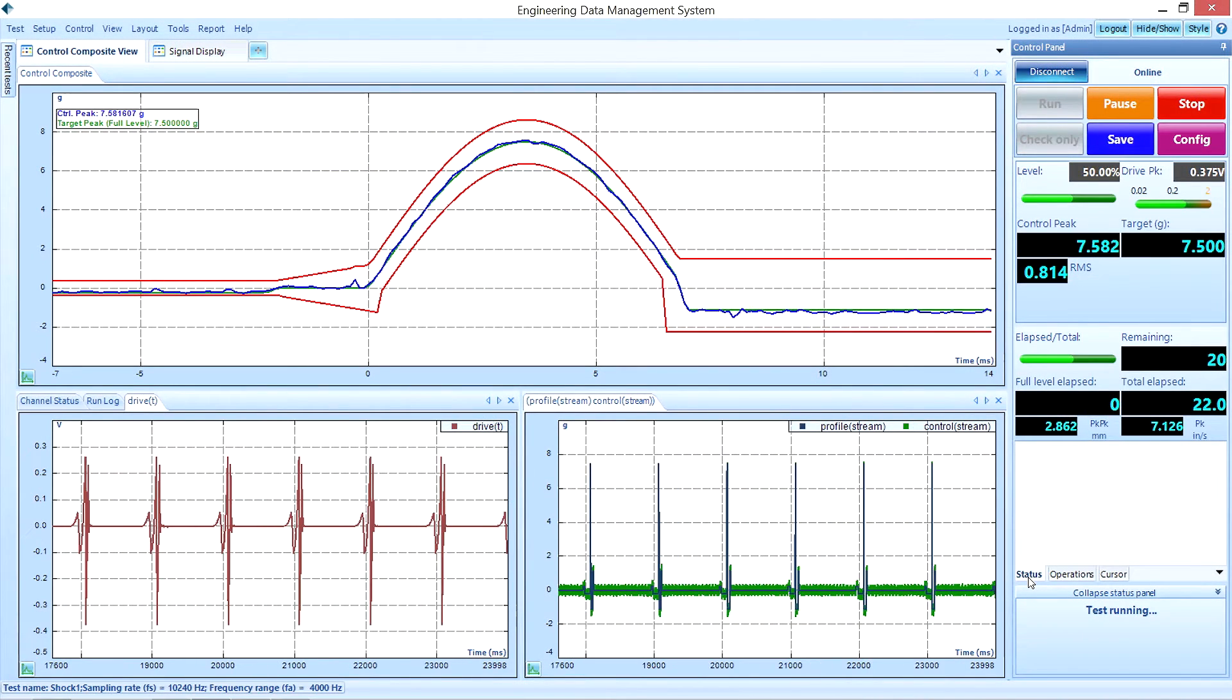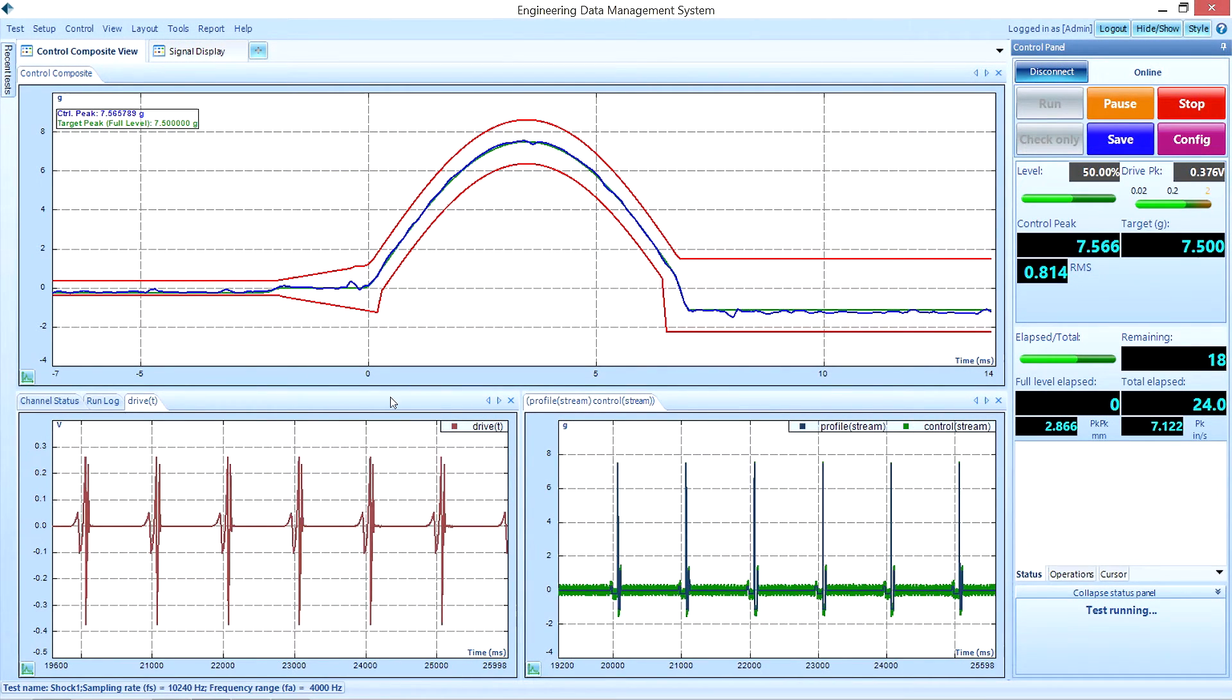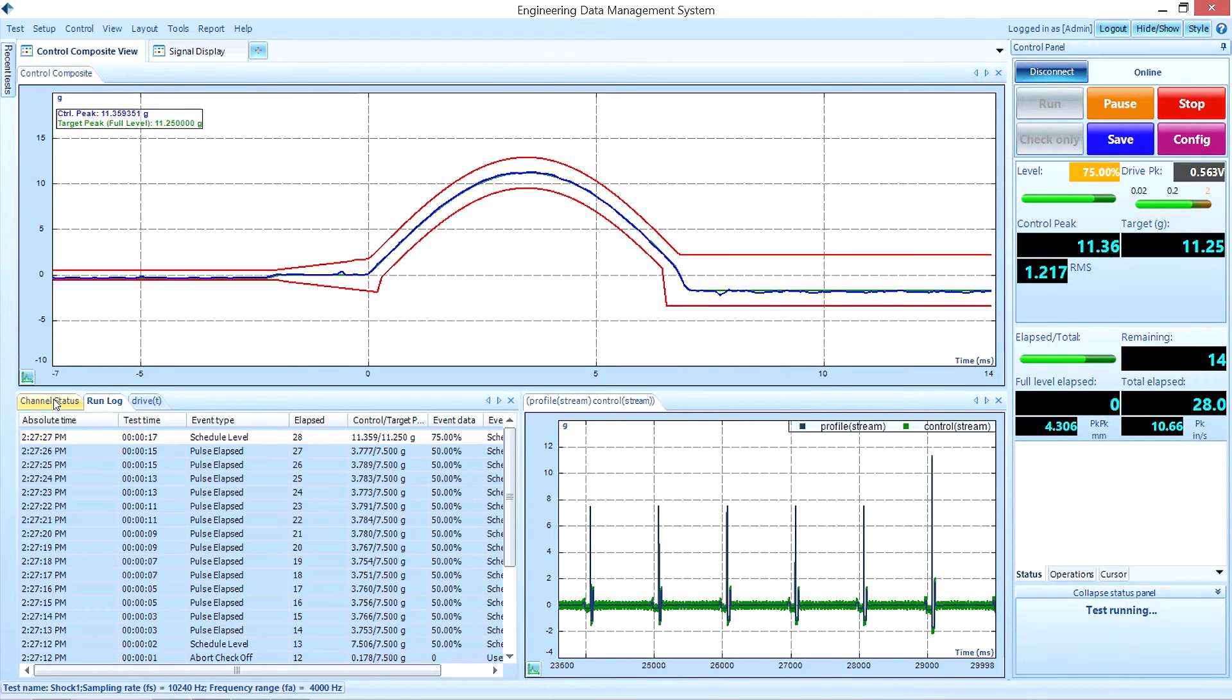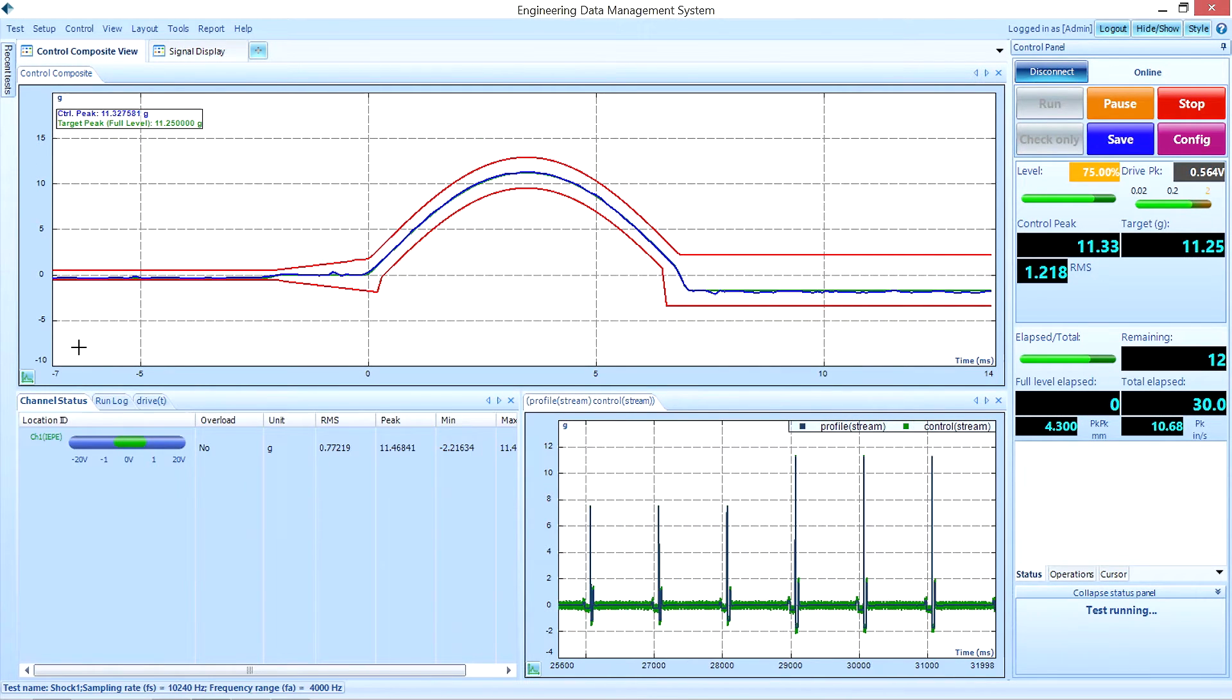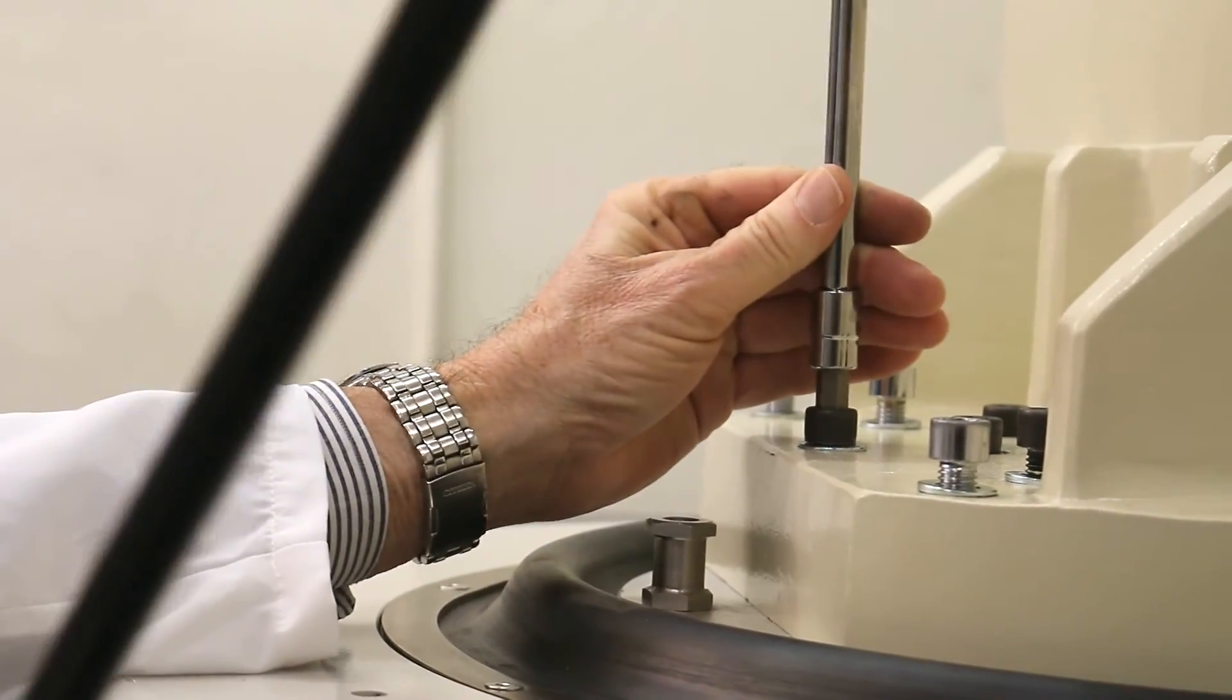Here is the control signal. It is the acceleration signal measured on the testing article. The closer the control signal can match the defined pulses, the better. With this test, you can see the control signal matches the target profile very well.